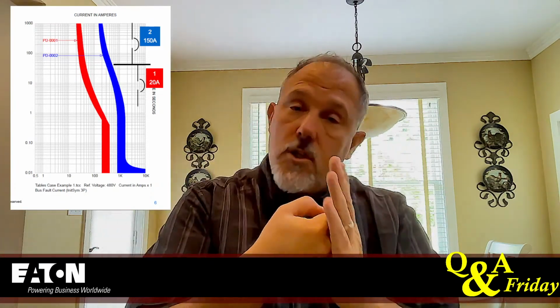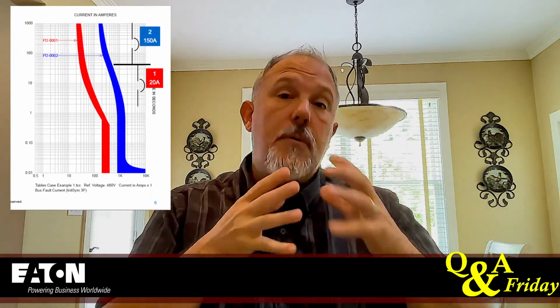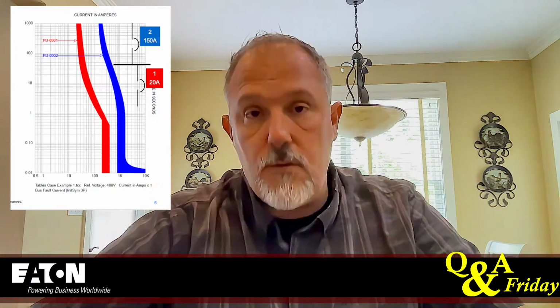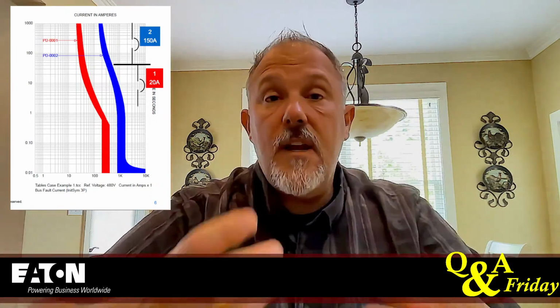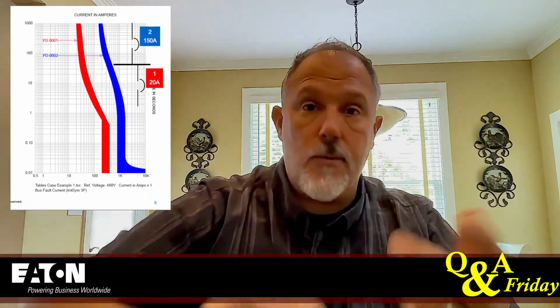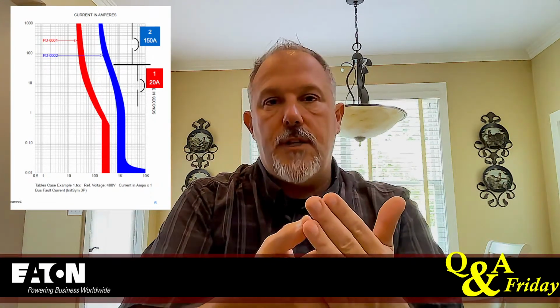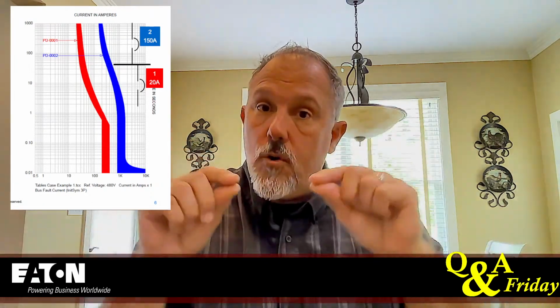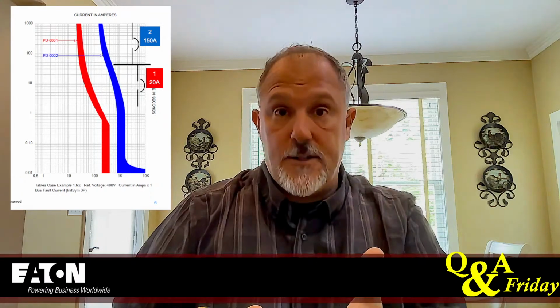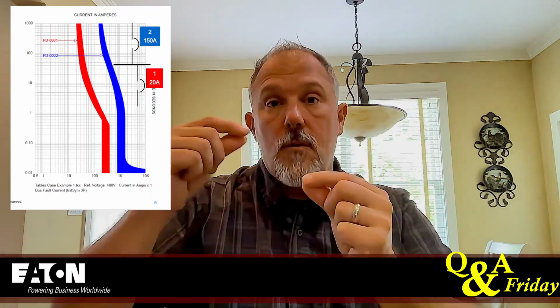So to hold those contacts closed, I need physical pressure. How do I do that? I do that with springs. I do that with beefing up the levers, beefing up the hinges. Right? There are hinges in there that the contact has to rotate on. I have conductors that have to hold that mount on those hinges. So if I make the metal bigger, I need to think about that little flexible copper braided conductor that connects that arm with the heating element.